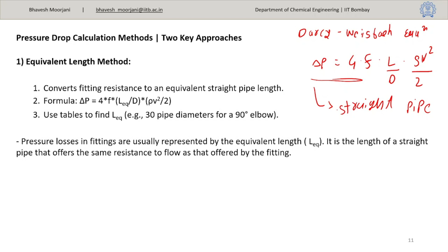So there are two approaches. One is this equivalent length method, so this is the first method, and second method is the K method. We will come to that, but it's finding a K constant for a fitting and from that the pressure drop calculation is done, right? So what happens in the equivalent length method? What is equivalent length, L equivalent? First let's understand that this L equivalent is the equivalent length of a fitting.